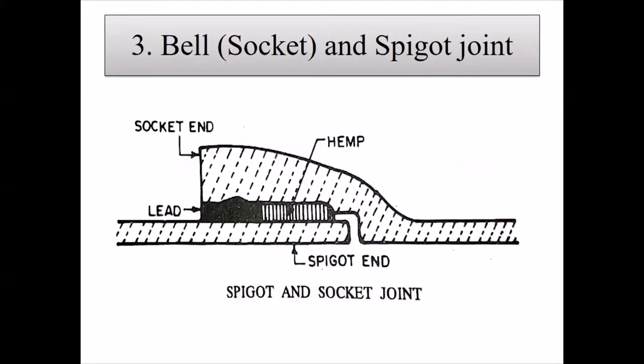In the bell and spigot joint, the plain end of the pipe is known as the spigot end and the extended end is known as the bell end. Yarn or hemp is bound around the spigot end and a rubber gasket is placed tightly over the yarn. The spigot end is then inserted into the bell end such that it is properly set in position.